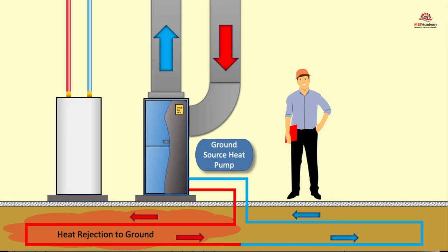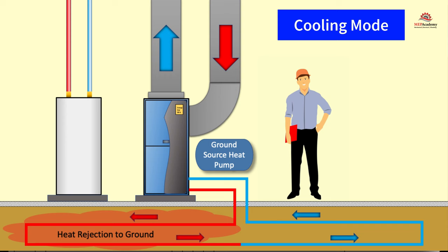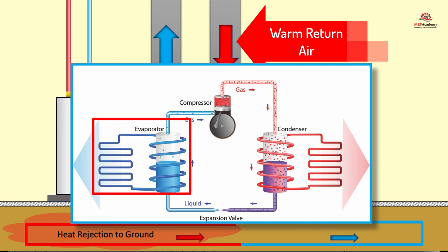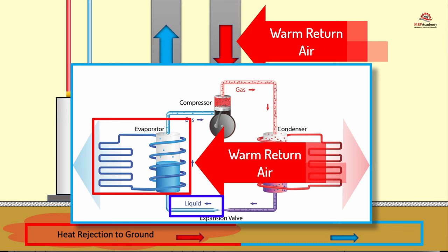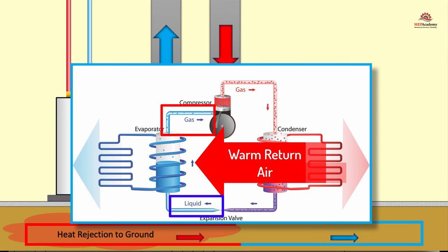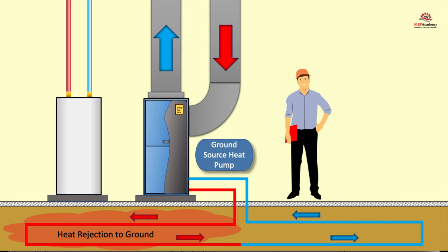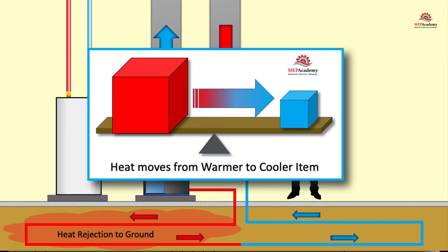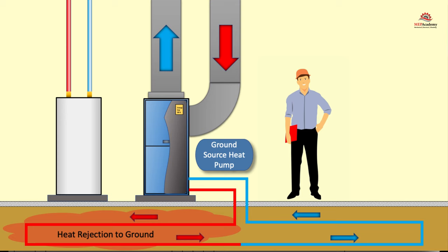In cooling mode, warm air from within the building is brought into the ground source heat pump. The heat pump's indoor coil will absorb the warm air into the cooler liquid refrigerant circulating through the coil. Absorbing the heat will cause the refrigerant to boil and turn into a gas. The refrigerant will circulate through the system and be absorbed by the cooler water circulating through the system from underground. The heat is then absorbed by the water and circulated underground where the heat is rejected to the cooler ground. The second law of thermodynamics states that heat moves from a warmer to a cooler item. The water and refrigerant never come in contact with each other.